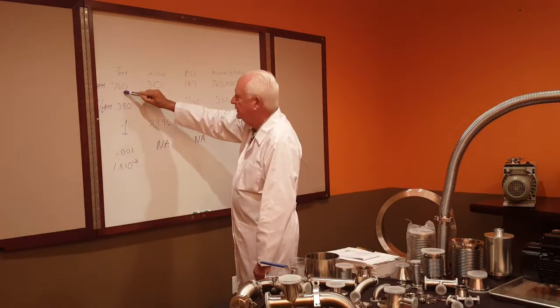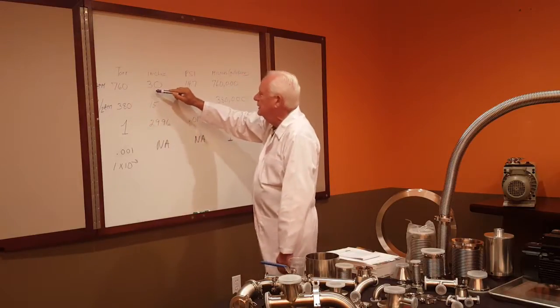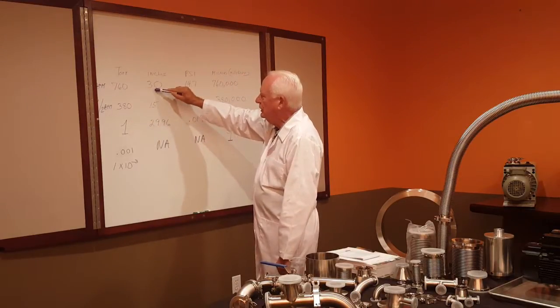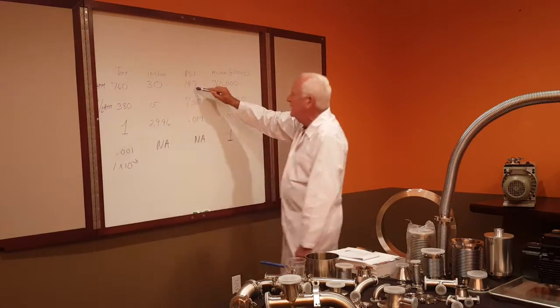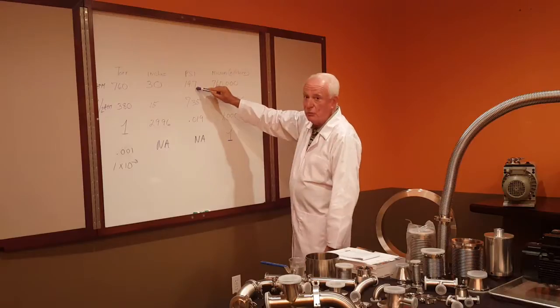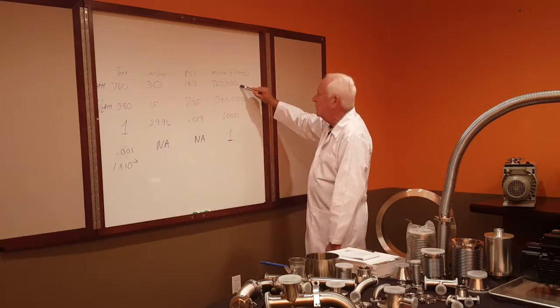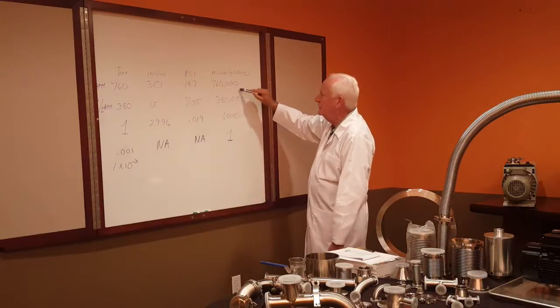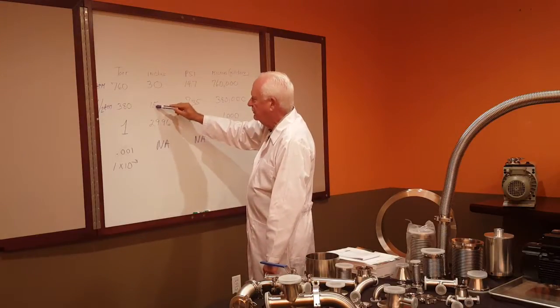That is 760 millimeters of absolute mercury. Over here we have 30 inches, which there are 25.4 millimeters in an inch. And then we have 14.7 pounds per square inch at sea level at atmosphere. And another term they use, microns or millitorr, 760,000. This is an atmosphere.